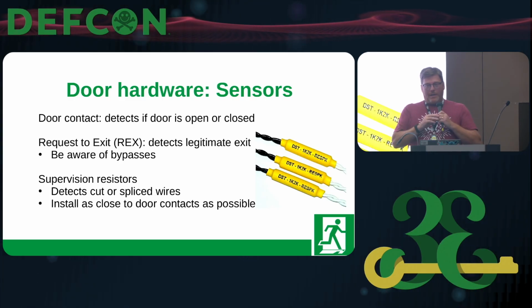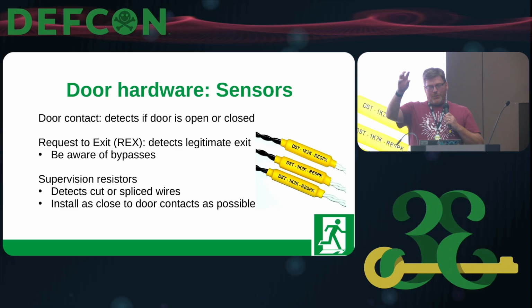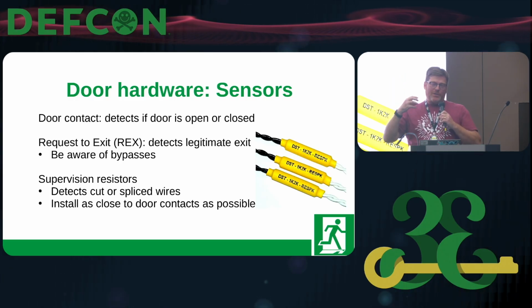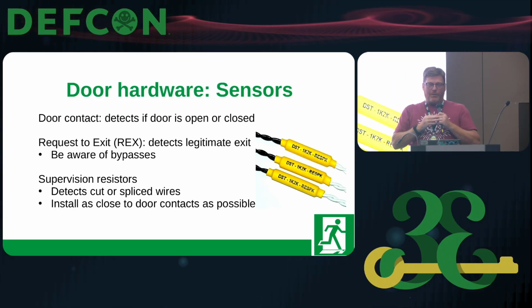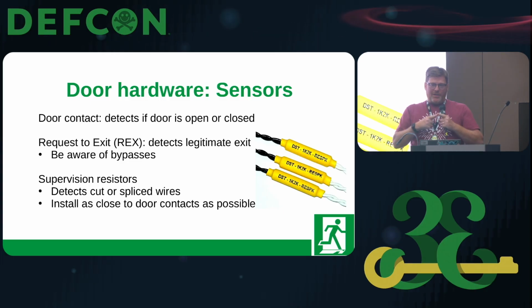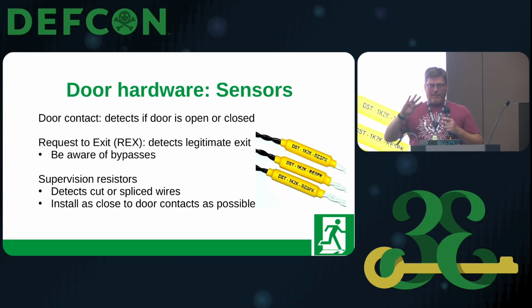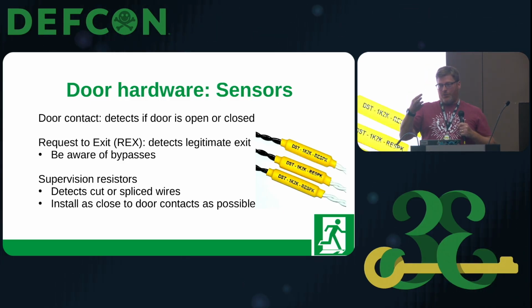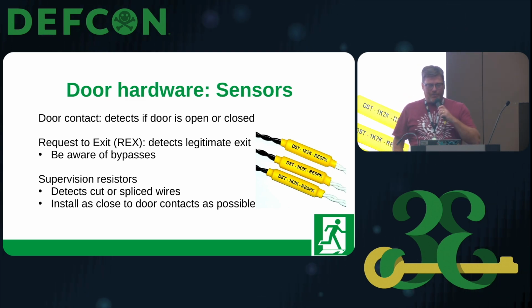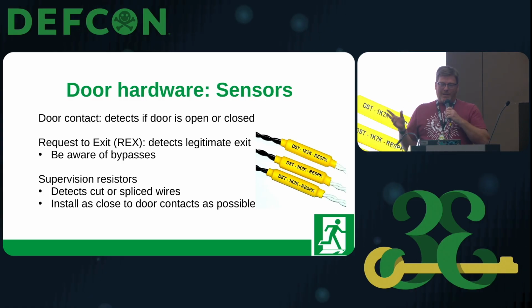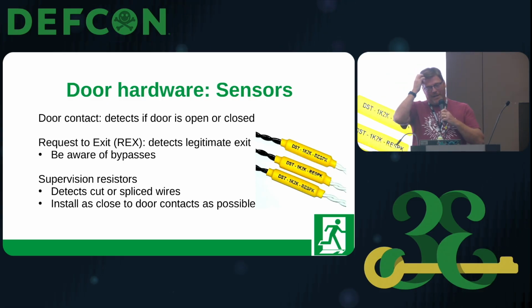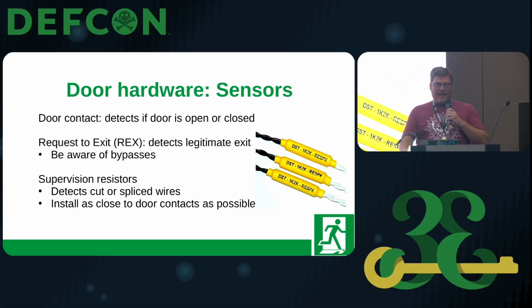These are put in line as close to the door contact as possible, and they change the signal from just this line is open or this line is shorted to four different resistance levels: this line is shorted, this line is open, or the door is open, or the door is closed. So it allows the system to detect if somebody cuts the wires or splices them together, or the door contact falls off, and it helps you troubleshoot better. These things are like $1.50. It is sheer laziness that companies do not install these.